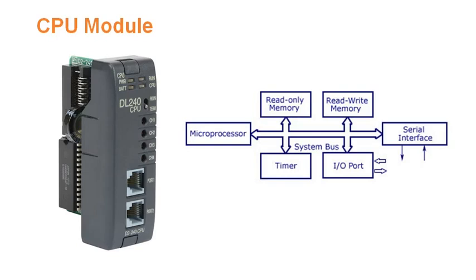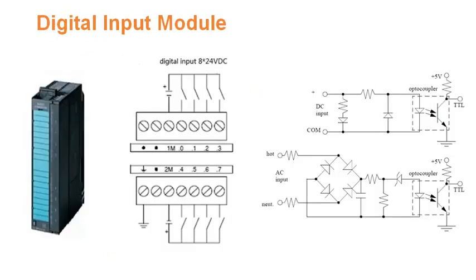The CPU module, which is the decision-making module of the PLC, consists of a microprocessor, RAM, flash memory, I/O ports. I/O ports are used for connecting to the input and output modules of the PLCs. In addition to this, the CPU also consists of a serial interface or Ethernet interface. These interfaces are used to connect to the PLC programmer or to the SCADA system.